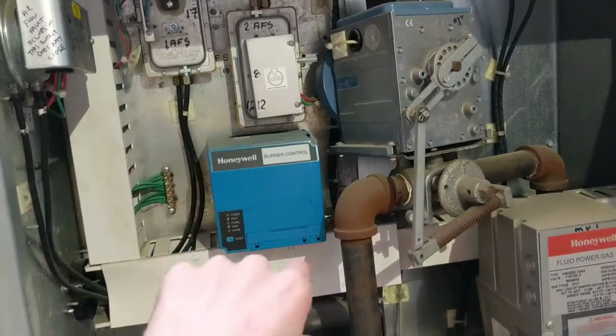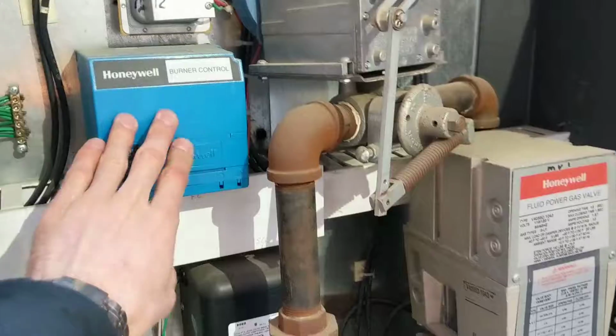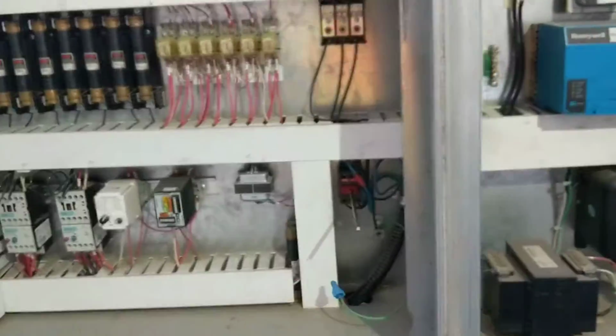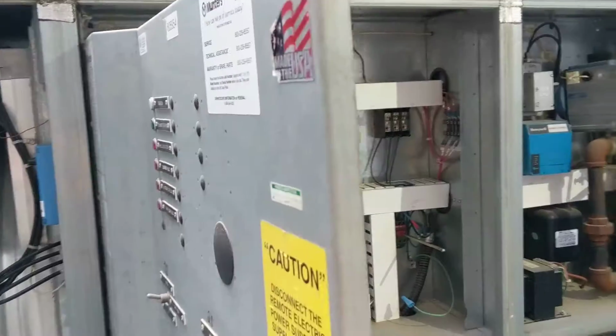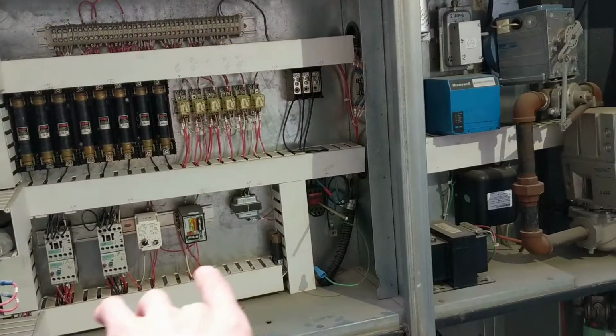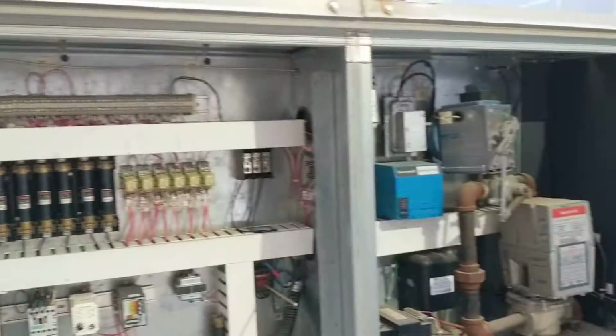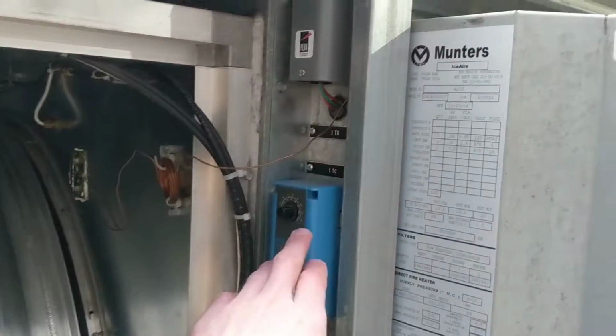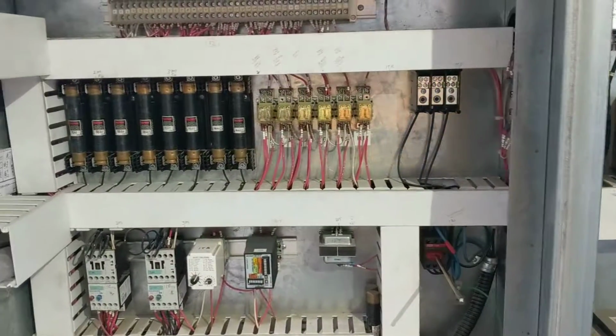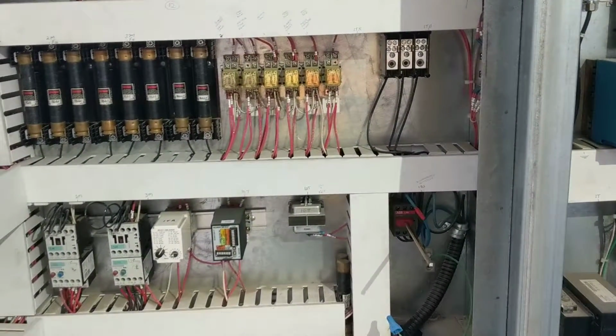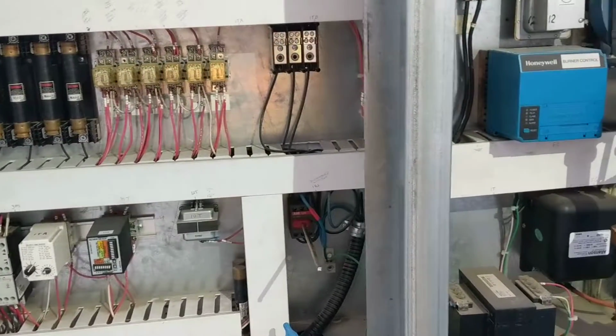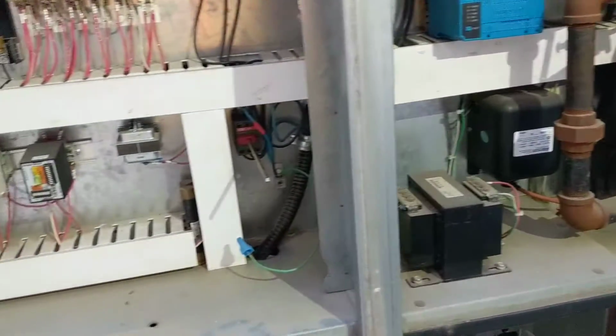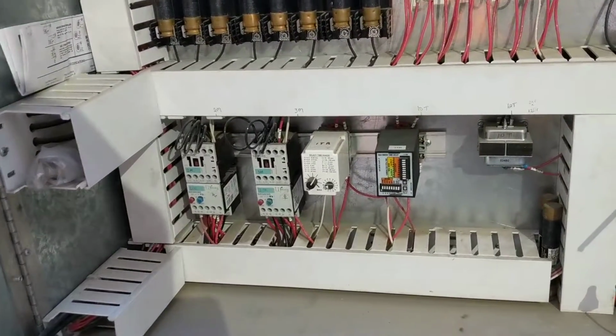As I said, both motors were replaced recently, and all of these parts here, just about, we don't have a spare one of these, but we have a lot of spare parts for this unit in the C-can. That includes spare relays, starters, timers, spare airflow switches, and spare stats. So just about anything that can fail on here, there's going to be a spare part in the C-can. And hopefully that gives you a good overview of how to troubleshoot this unit and what to look for when you're trying to find the problem.